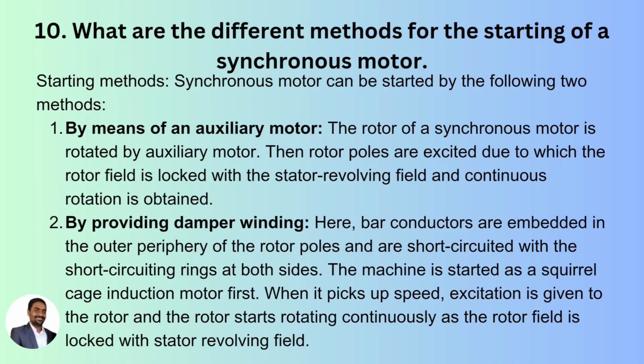What are the different methods for starting a synchronous motor? A synchronous motor can be started by the following two methods: by means of an auxiliary motor method and by providing a damper winding method. In the auxiliary motor method, the rotor of the synchronous motor is rotated by an auxiliary motor. Then the rotor poles are excited, due to which the rotor field is locked with the stator revolving field and continuous rotation is obtained. In the damper winding method, bar conductors are embedded in the outer periphery of the rotor poles and are short-circuited with short-circuiting rings at both sides. The machine is started as a squirrel cage induction motor first. When it picks up speed, excitation is given to the rotor and the rotor starts rotating continuously as the rotor field is locked with the stator revolving field.